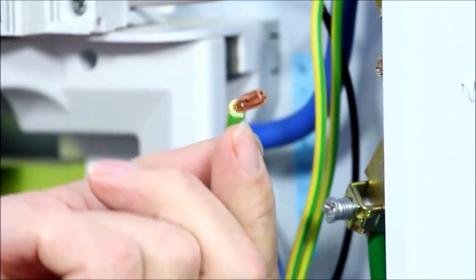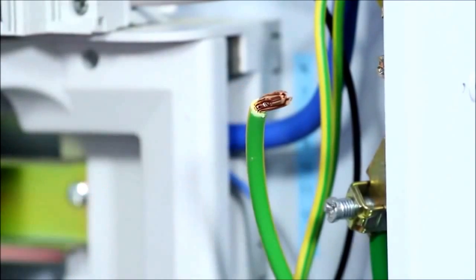So a good way of measuring it is by length. For a 10mm bonding conductor, up to about 25 meters would be okay. If you get above 25 meters, you should really be looking at a 16mm bonding conductor. But we'll carry out the test anyway.